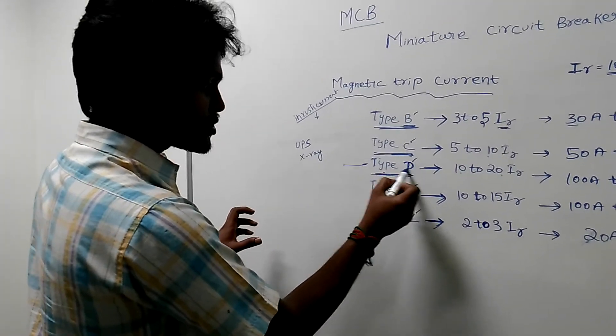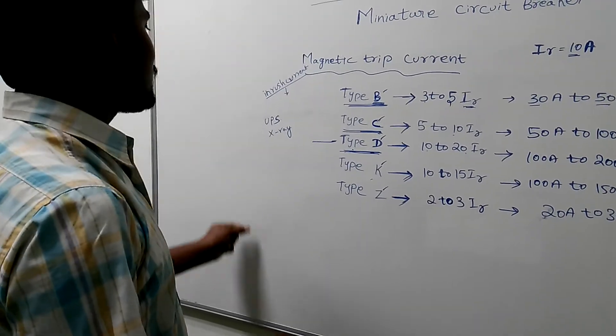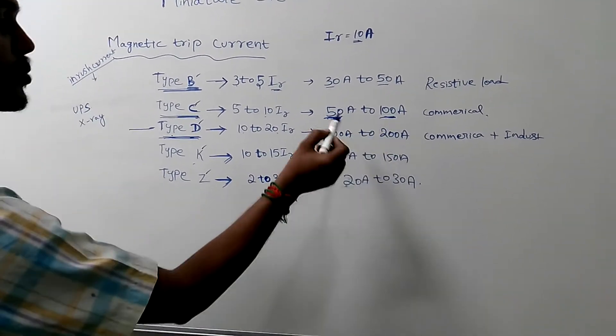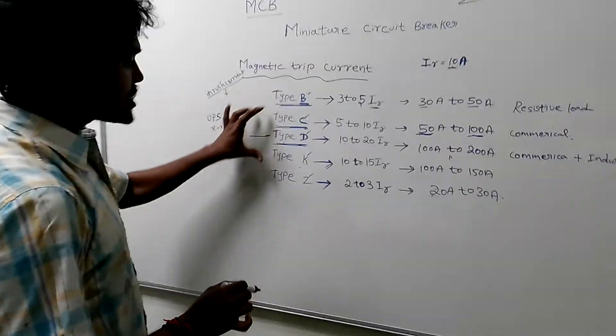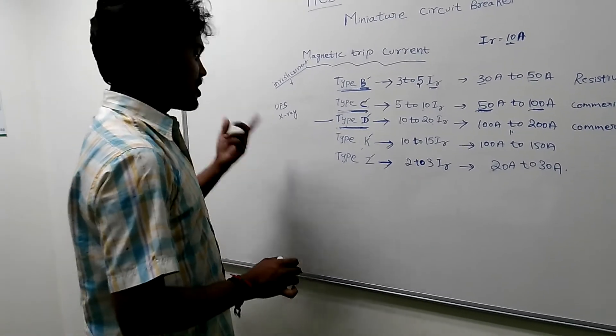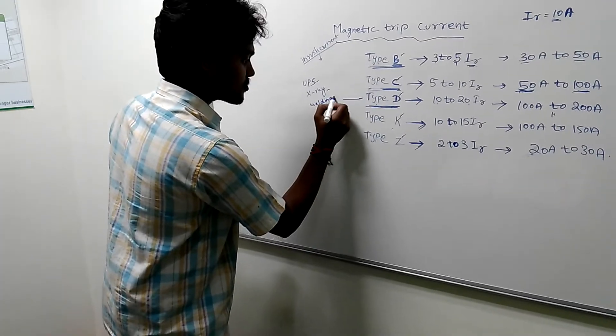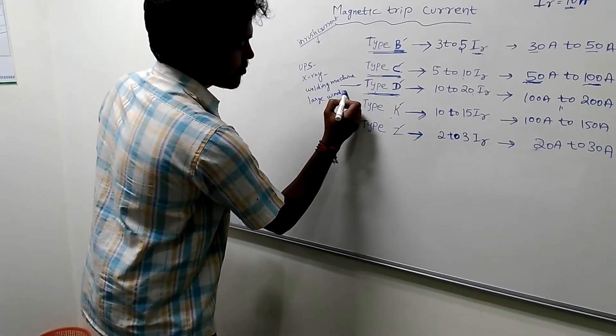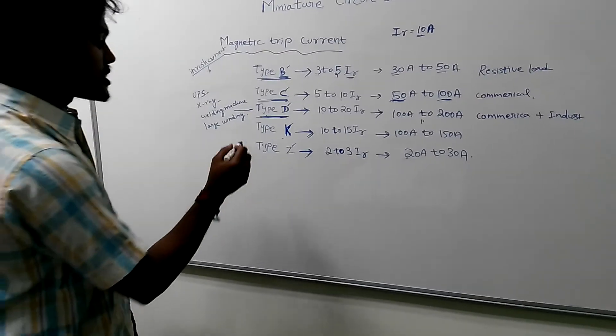Type D is used for high inrush current applications. It is used in UPS systems, x-ray machines, and industrial welding. It is also used for large winding motors and large motor protection as well as transformer protection.